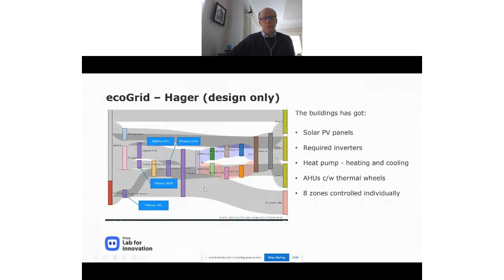The conclusion: starting from a maximum contract capacity of 140 kilowatts, by just applying EcoBuilding without a battery, we could decrease the contract capacity from 140 kilowatts down to 100 kilowatts.